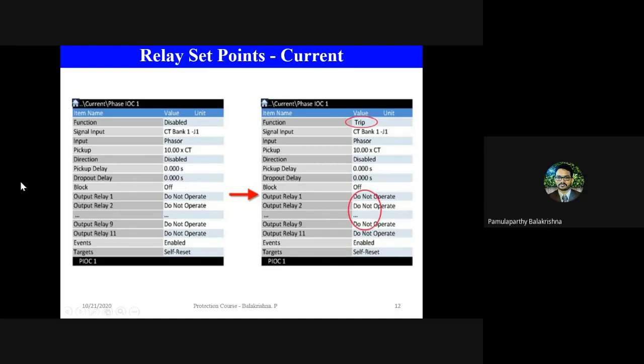Fine. Thank you. So then you have a block function. Basically, block means the function will execute if it is enabled. The moment you set block to on, it will measure everything, it will compute everything, but it will not trip the breaker. Basically, it will not take any control action. Why this feature is kept: when you are testing, installing or commissioning a relay, you may require an option where you want to see how the relay is measuring various signals, how accurately it's measuring, but you do not want to trip a live breaker which is connected to the system. In that case, you use this block function. So block is nothing but the protection will run, but the control will not happen.